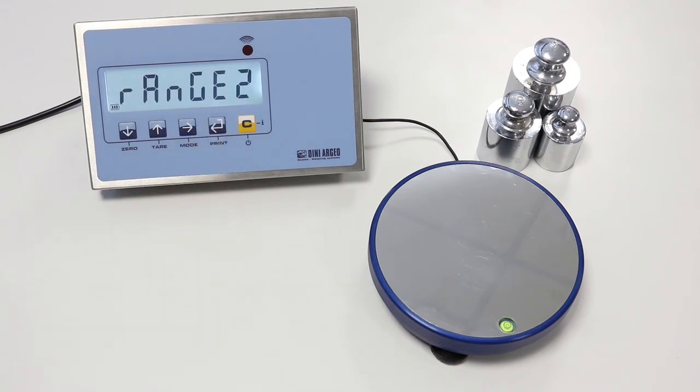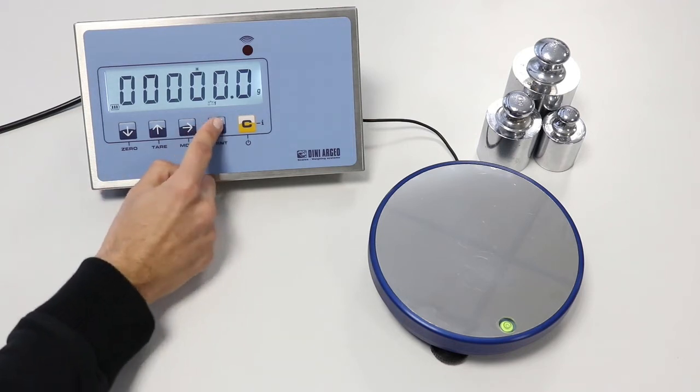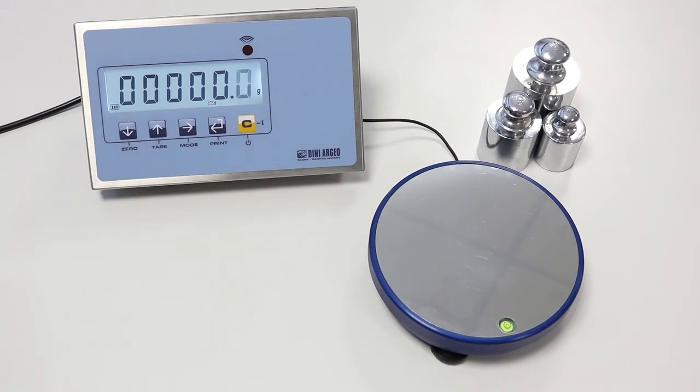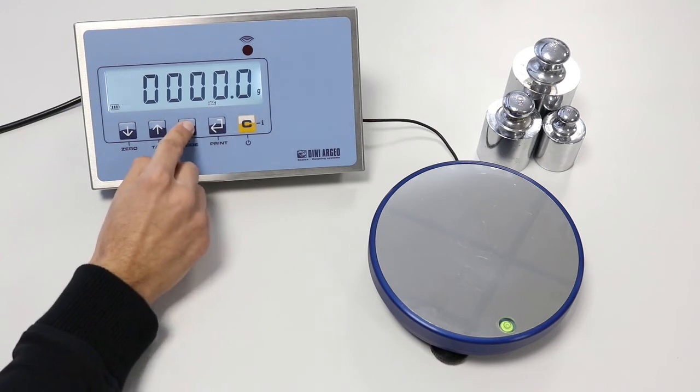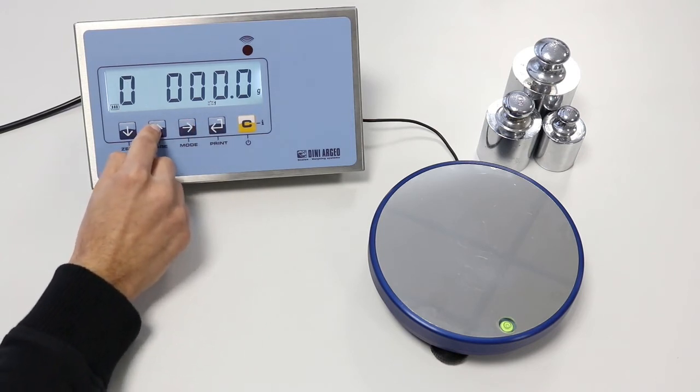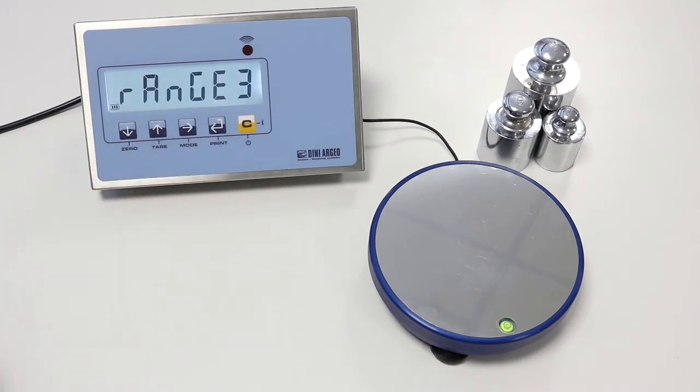Range 2 has to be programmed only in case of multi-range scales. It is the second range. For our example, we need to set it to 3000 grams. Range 3 is needed only for multi-range scales. It is the third range. We do not need it for our example, so we skip it.